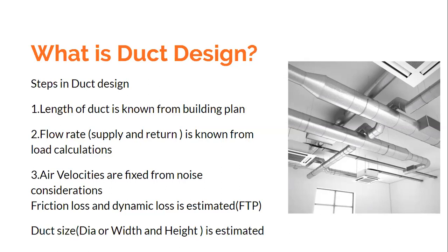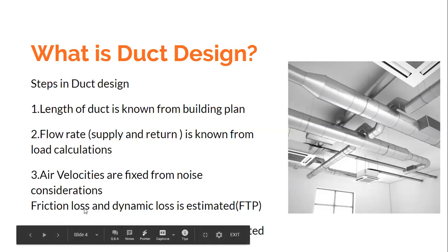As explained in the load calculation videos, the output of load calculations is: one, we know the apparatus dew point of the coil for cooling and dehumidification; and two, we know the flow rate. The velocity of air to be supplied is generally fixed from noise considerations, which I will explain in another video. Once you know all those things and the duct lengths, you can make a fairly good estimate of the frictional losses and dynamic losses. The frictional losses can be estimated using the friction chart — that is the topic of this lecture.